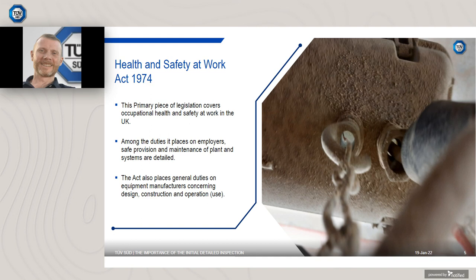In the photograph in the slide, whoever installed this light modified the casings in the hangar for the gland. The gland was installed but was oversized. The certification for the light was invalidated due to the unauthorized modifications, and the EX integrity of the unit was compromised. It was potentially dangerous. In this instance, there were several lights all installed like this. An initial inspection would have picked this up, but of course, at that point, the damage was done. The manufacturer had supplied a product that was, as far as reasonably practical, safe. The employer, however, did not take an interest in his contractor's activities, nor did they audit or review.